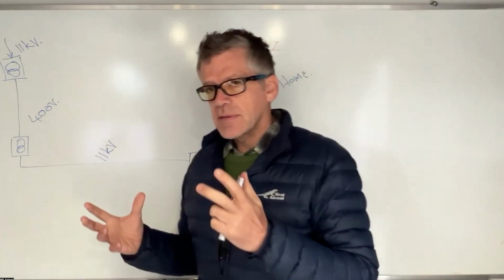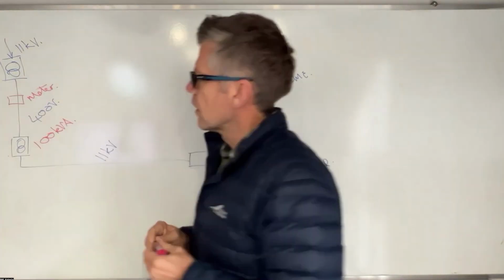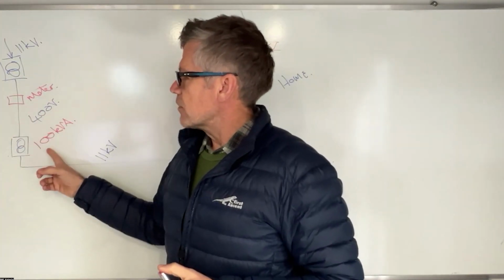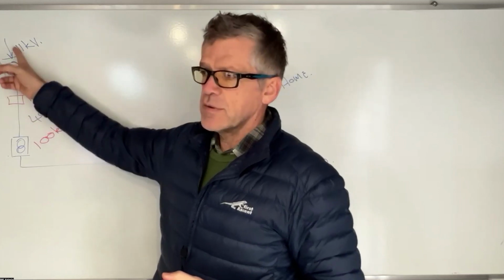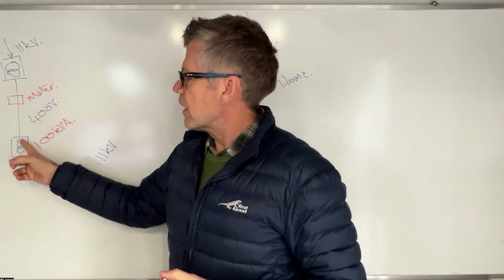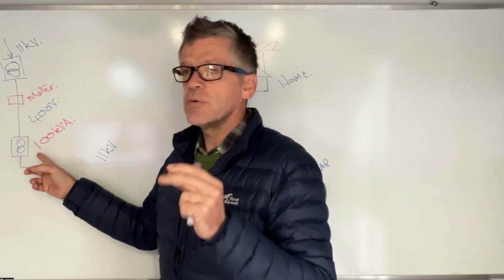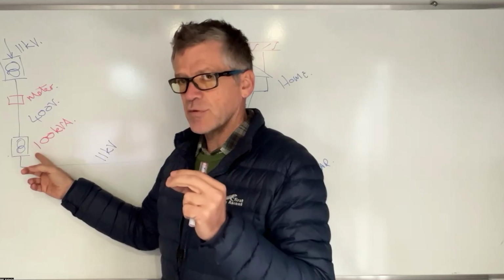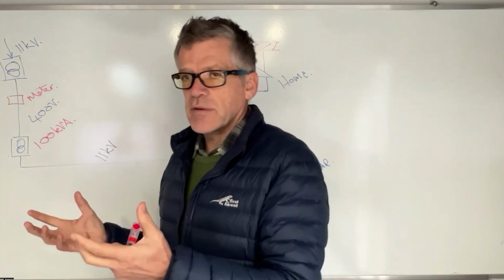Quick look at this site. The site is on a wine farm. Meter sits over there, 100 kVA transformer. So it comes into the property through this transformer over here, through the meter, and then goes through a step-up transformer. You would be surprised at the consumption that a transformer has just in operating.